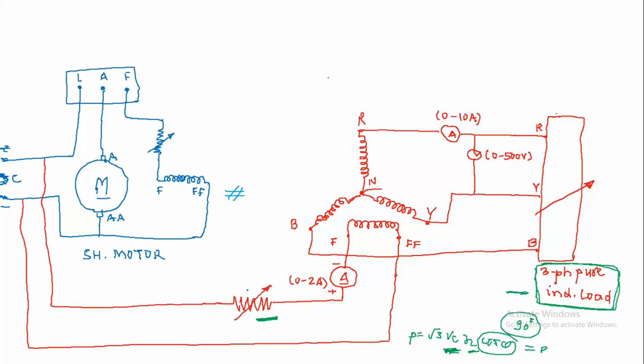Once you set its speed at 1500, throughout the experiment it remained 1500. Even though current is increasing, because the generator is not delivering any active power to the load, speed will not change, frequency will not change. Once you set frequency or speed rated, it will not change.